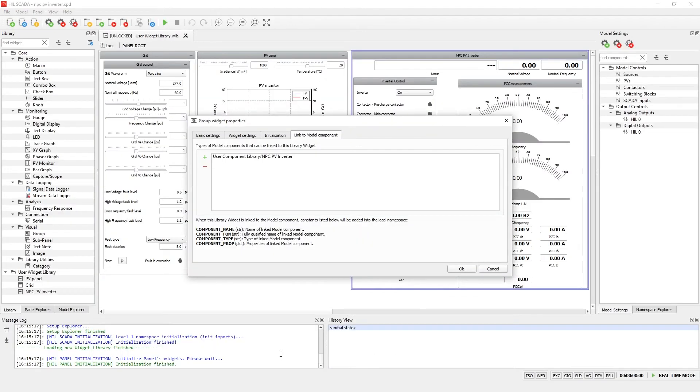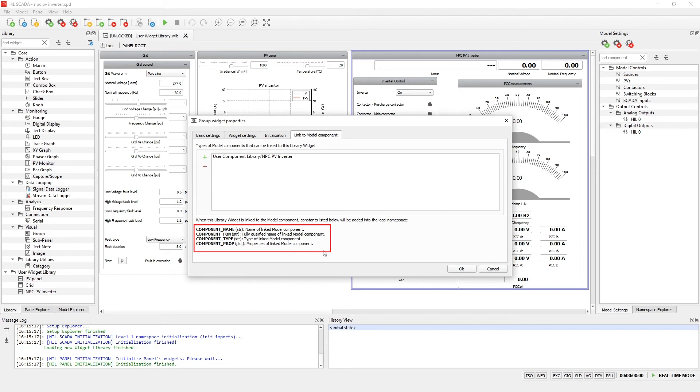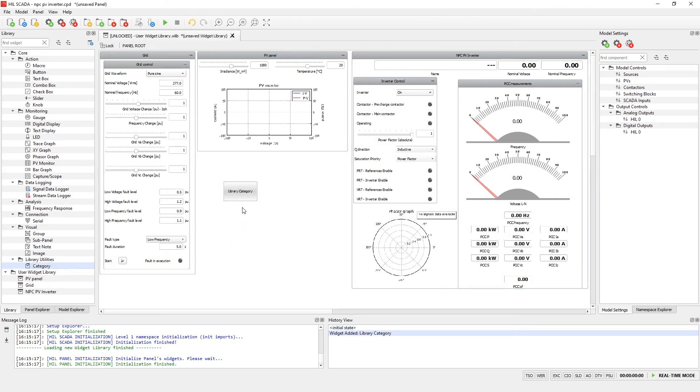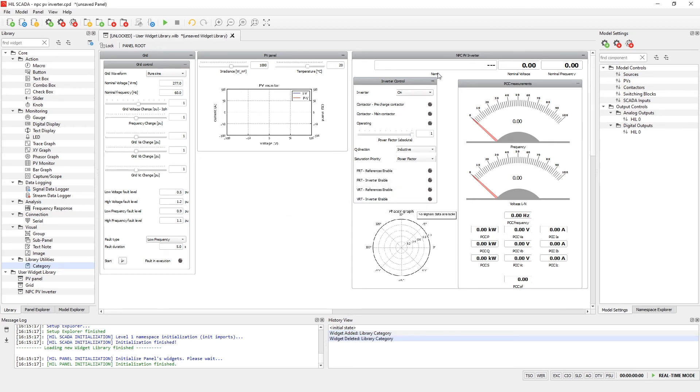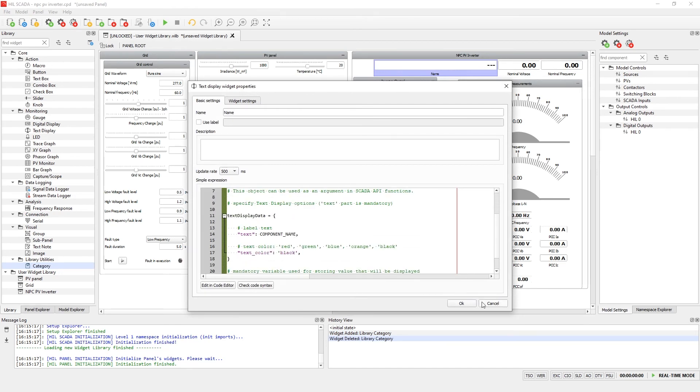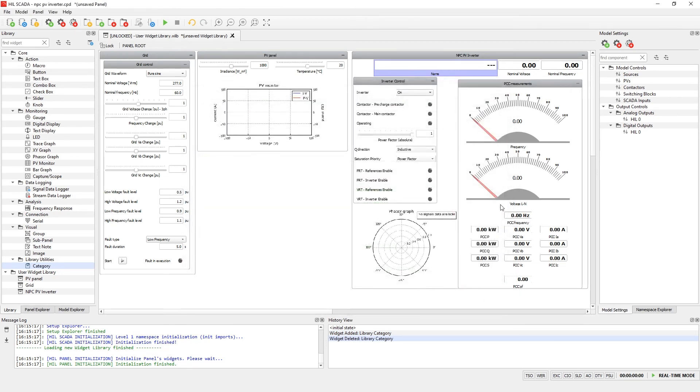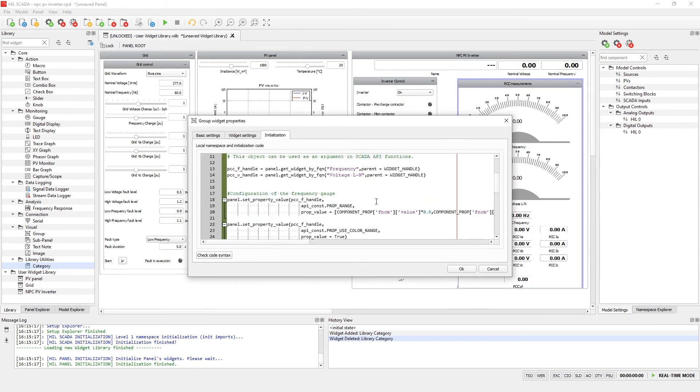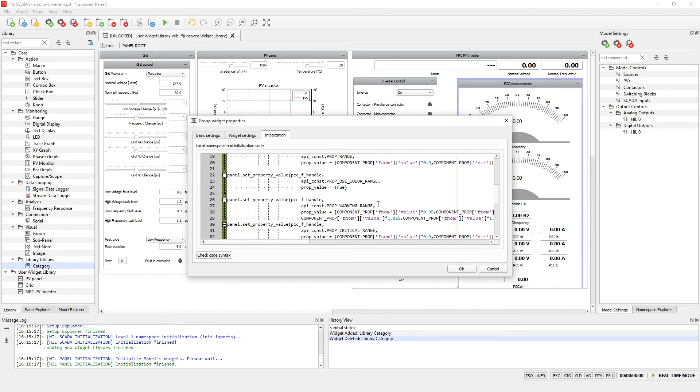The link between the component and the widget will automatically add variables to the local namespace of the group or subpanel. These variables are component name, component fully qualified name, component type, and the dictionary of the component properties of the linked component. These variables together with SCADA API are useful in order to configure the widget. Widgets in a user library can be placed at the root level or organized using category components. A category widget is a specialized subsystem widget used exclusively in libraries. It can contain any number of widgets including other category widget instances. In this example the name of the inverter text box, nominal voltage display, and nominal frequency display widgets are configured using auto-generated variables from the local namespace of the group. Also, critical and warning ranges in the two gauges widgets are configured using component properties from the linked NPC PV inverter component.